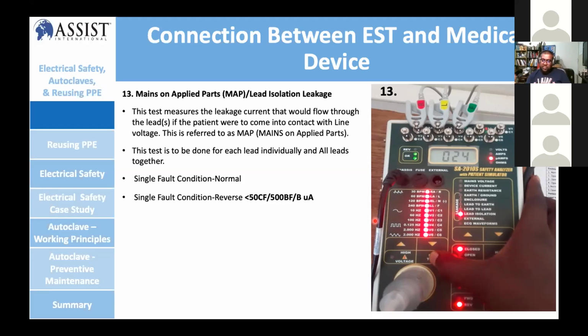So when one of the lines has contact with 110 or 220 voltage, the other leads should measure less. That's what you're measuring actually. For example, you see it shows 24, which is below 50 for CF. That means it's in good condition actually. So this is on the applied parts. So this is how you do electrical safety tests by using the EST analyzer.